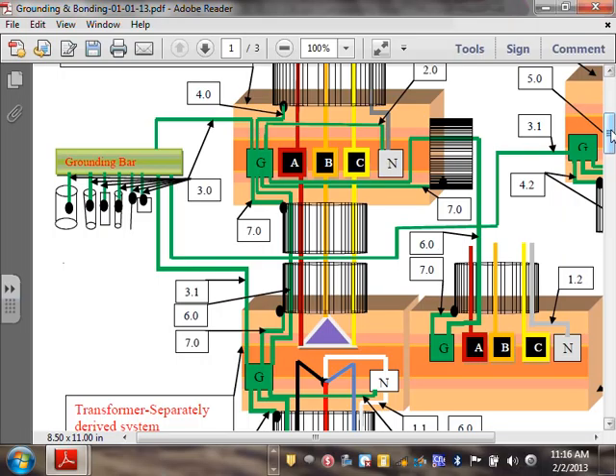Floating neutral. If you have been in a building where the voltage goes up and down, right, and it dims and all this good stuff, you're looking at floating neutral. So any load that's tied between the phases and the neutral starts sharing the voltage based on their impedance. The biggest load will take more voltage. So you're dealing with open neutral, and when you deal with open neutral, you burn equipment.